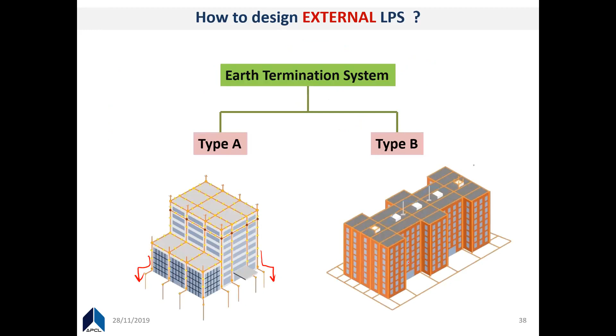So the requirements are as given, and the selection of materials, as I mentioned, for air termination and down conductors, there are given materials with specified cross-section areas. If you take a 25 by 3 metal tape, that's 75 millimeters squared. For copper, if it's a solid tape, the requirement is 50 millimeters squared, but here you have 75, so that's good. The thickness shall be 2 millimeter minimum, and here we have 3 millimeter, so that's also satisfying.